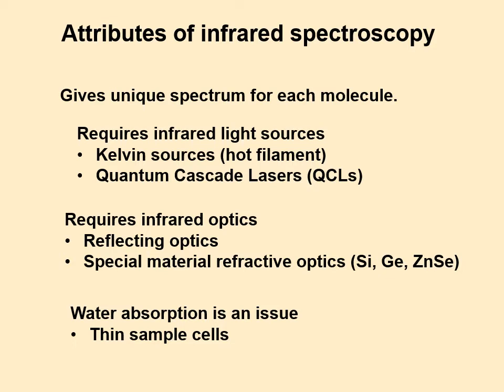Also note that the optics are different: glass does not transmit mid-infrared light — it will just appear opaque. So you have to use reflecting optics or special materials that allow infrared photons to pass through, like silicon, germanium, or zinc selenide.